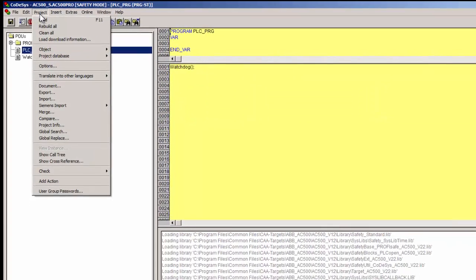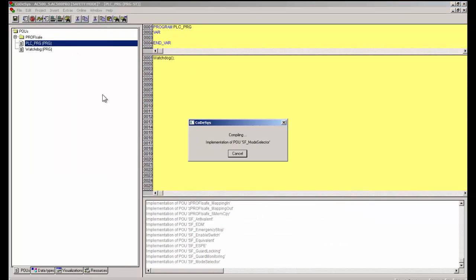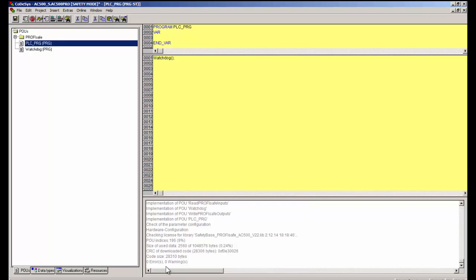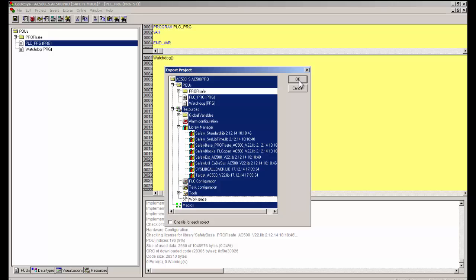The first step is to compile the IEC 61131-3 program without any error or warning. A compiled project needs to be exported as a text file for SEA Tool to analyze, as shown on the screen. Please remember to deselect the PROFISAFE folder and the Workspace Tool to avoid non-analysis of the export file by SEA.